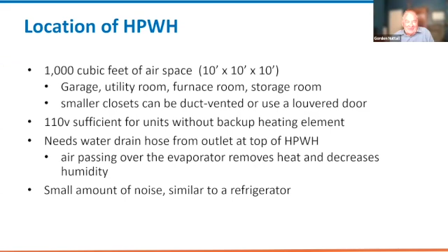It also needs a water drain hose, because the air passing over the evaporator on the top of the water heater is going to remove heat. It also decreases humidity, which means it's going to have condensation around those fins up there. So it does need a place to drain water to the outside if you're using a heat pump water heater, such as in a closet or some other enclosed area. And the other thing to consider with the heat pump water heater is that they do produce a small amount of noise, similar to a refrigerator. So if that closet is adjacent to your master bedroom or where you're going to be sleeping at night, it may not be the best choice unless you do other things. I've got a CPAP, and so the noise from that would certainly be greater than the sound coming from a heat pump water heater.